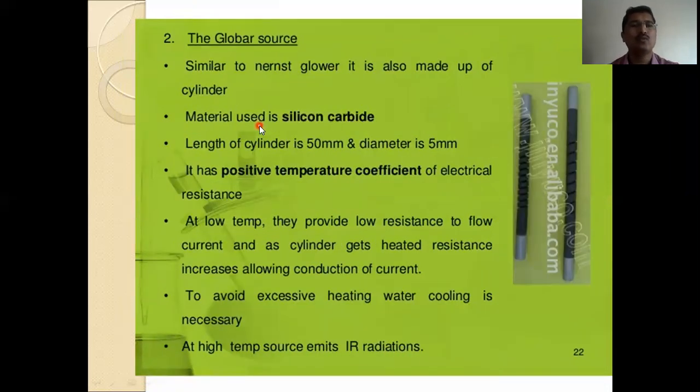The Globar source, similar to the Nernst glower, it is also made up of cylinder. Material used is silicon carbide. You can see here, length of the cylinder is 50 mm and diameter is 5 mm. It has a positive temperature coefficient of the electrical resistance. At low temperature, they provide low resistance to flow current, and as the cylinder gets heated resistance increases allowing the conduction of current. To avoid the excess heating, water cooling is necessary. At high temperature source, emits IR radiations.